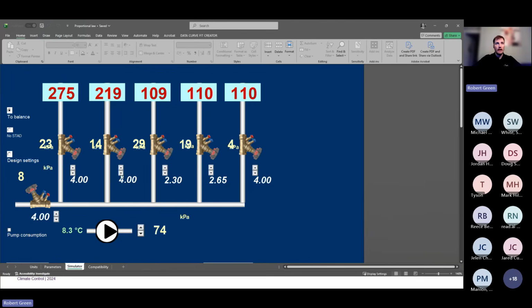And again, we go back upstream one more unit. If you've ever done any commissioning, this is why you will always commission from what we call the index or reference unit back towards the pump. It's because of this proportional rule, but we can actually see it in action here. So again, let's try. Okay, 18%, and these are all increased a little bit.